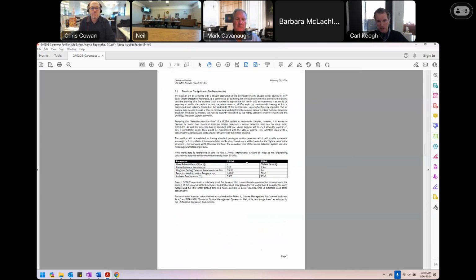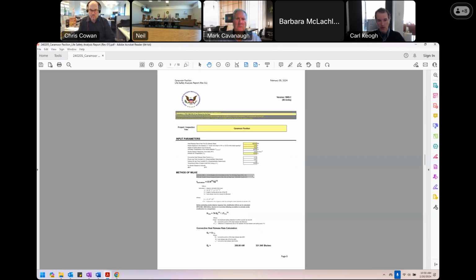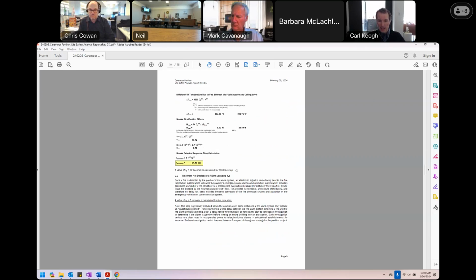So then the report goes through each component, calculating a time for each. The first component, on page 7, is how you determine the time it takes a VESDA smoke detection system to detect that a fire might be occurring within a structure. There's a series of calculations you can use, and these are excerpts from a spreadsheet used by the US Nuclear Regulatory Commission that can calculate these things.